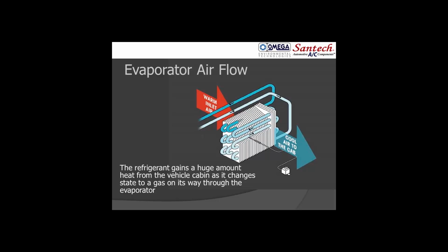So what goes wrong with evaporators? They're very protected. They don't typically get damaged from anything hitting it because it's in that evaporator case. What typically goes wrong with these things is they tend to get plugged up. Again, just like the condenser, the airflow through this thing, if that blower motor can't get air through, any dirt, dust, leaves, anything that's brought into the system, into the blower motor, tends to get stuck on the fins. Again, just like on the condenser, if you can't get airflow through there, you don't get that nice cooling coming out of the vents.